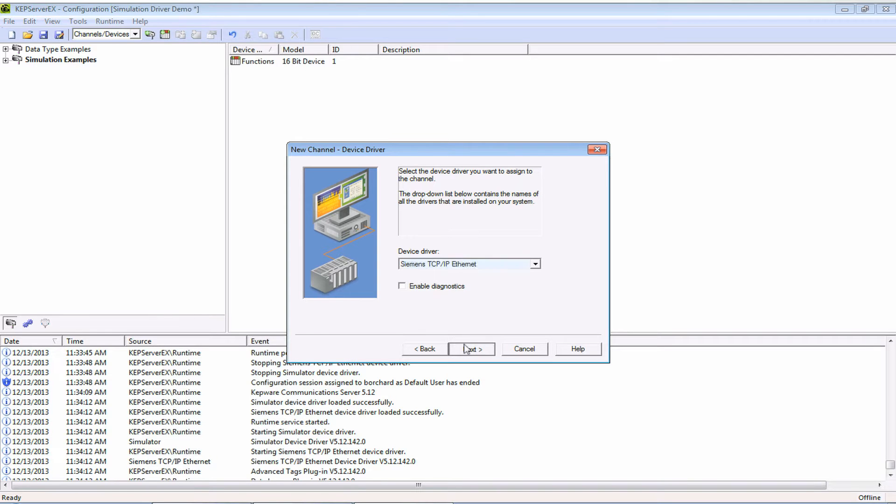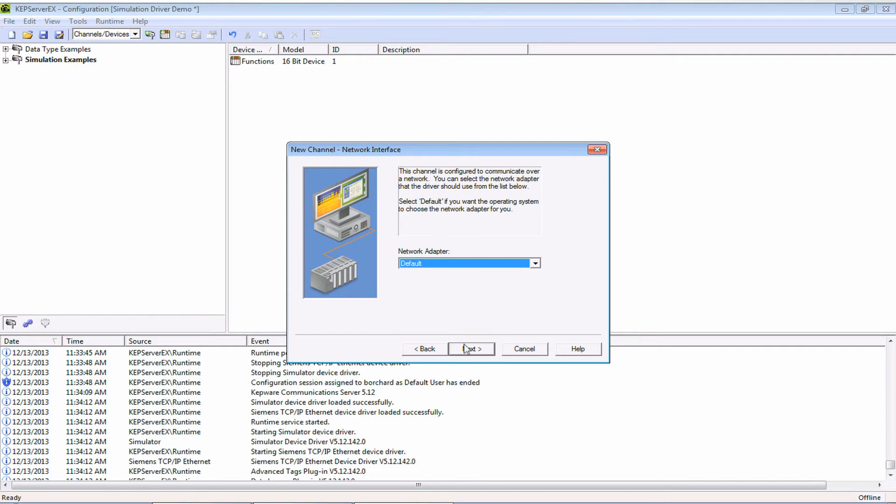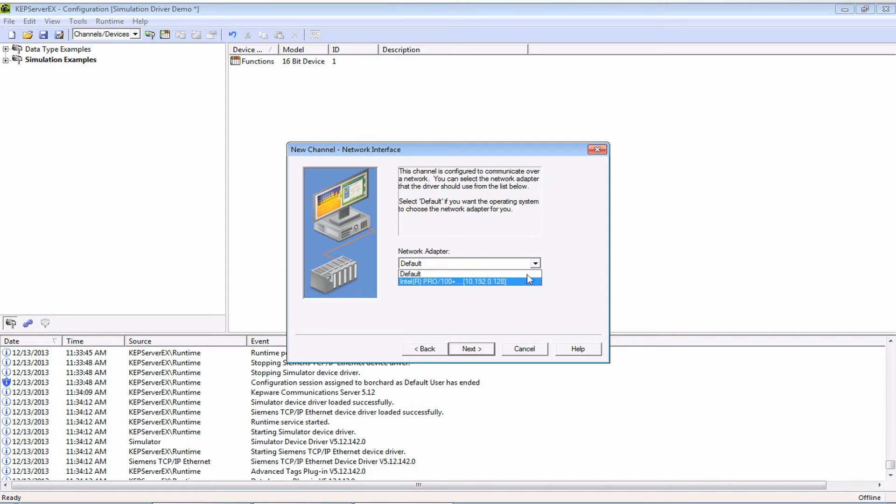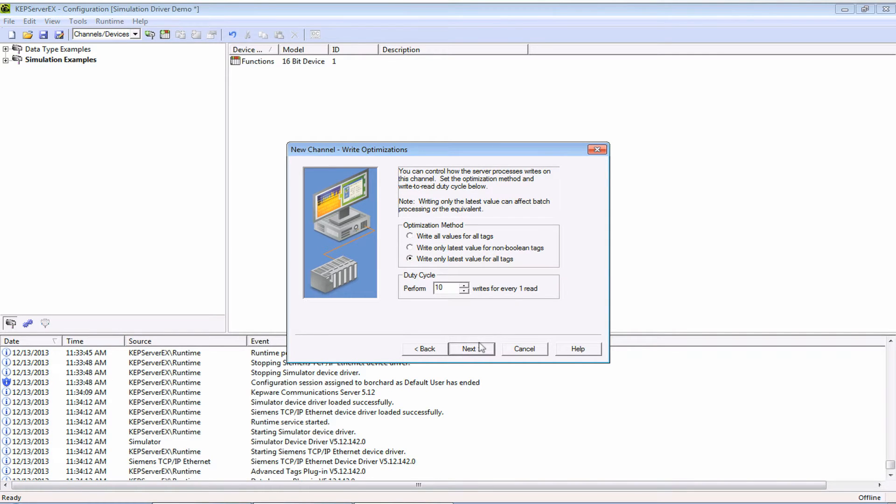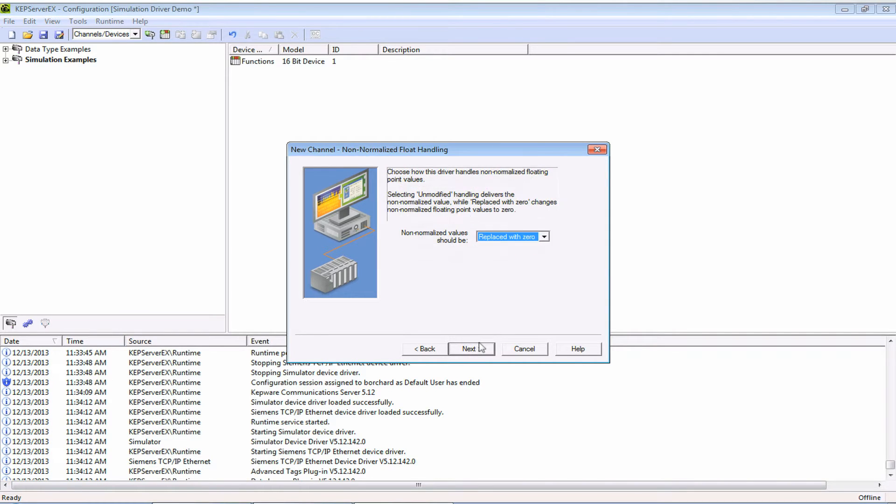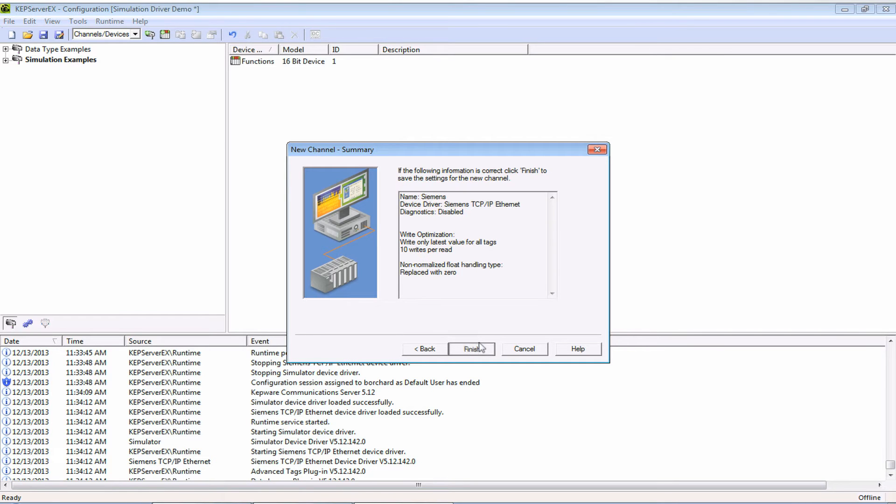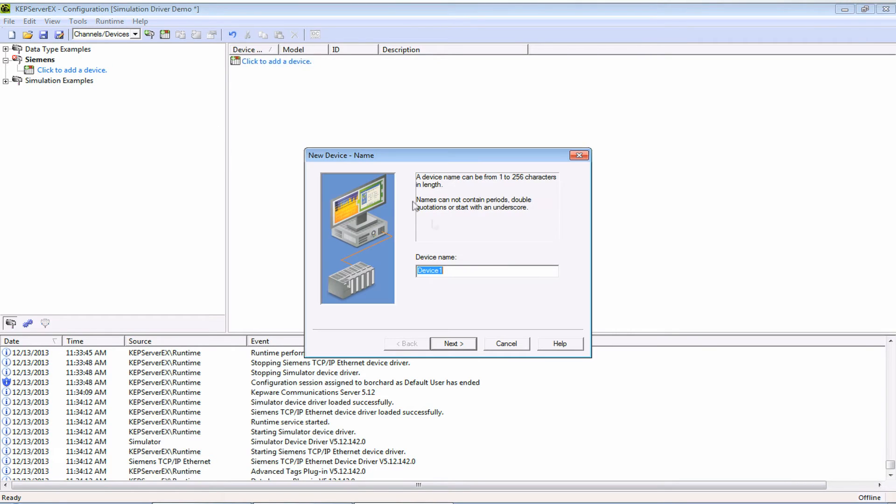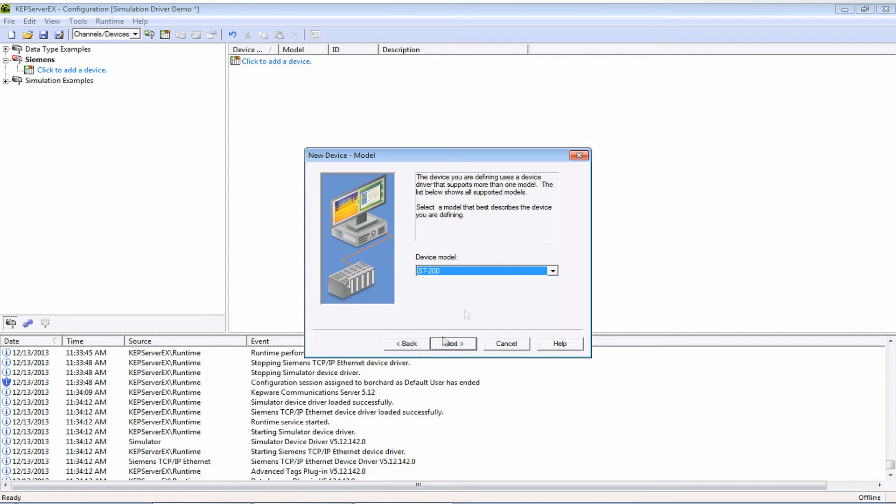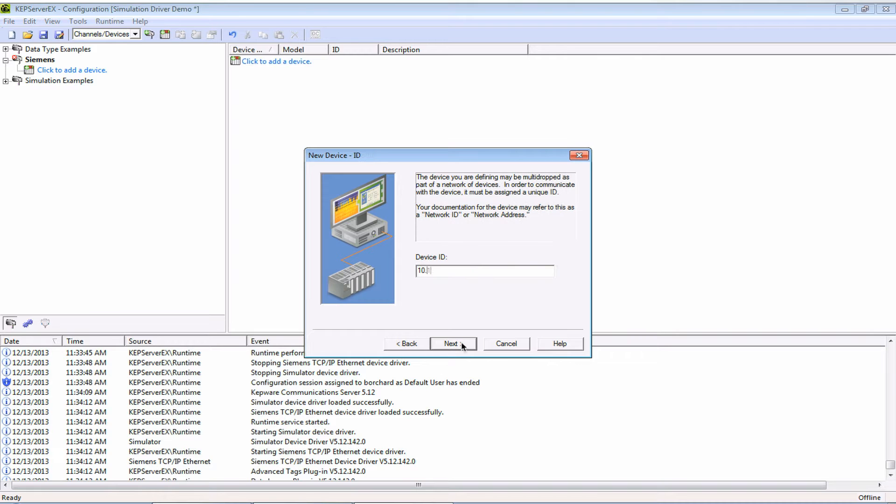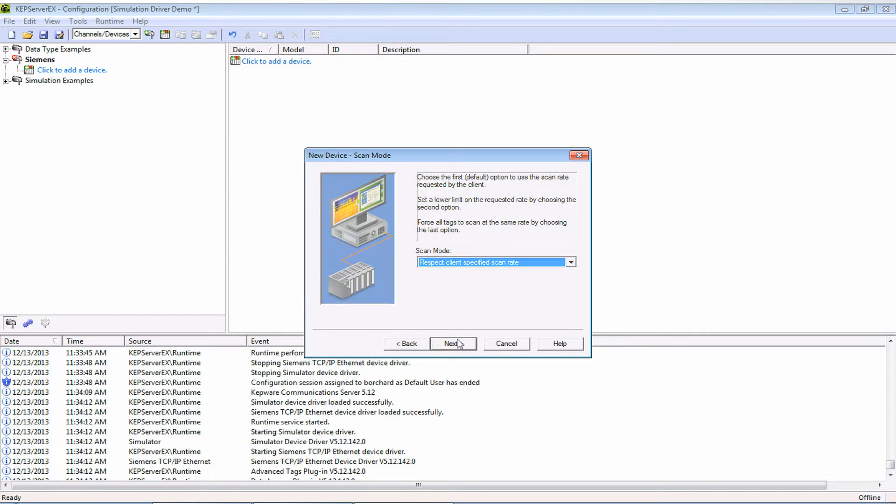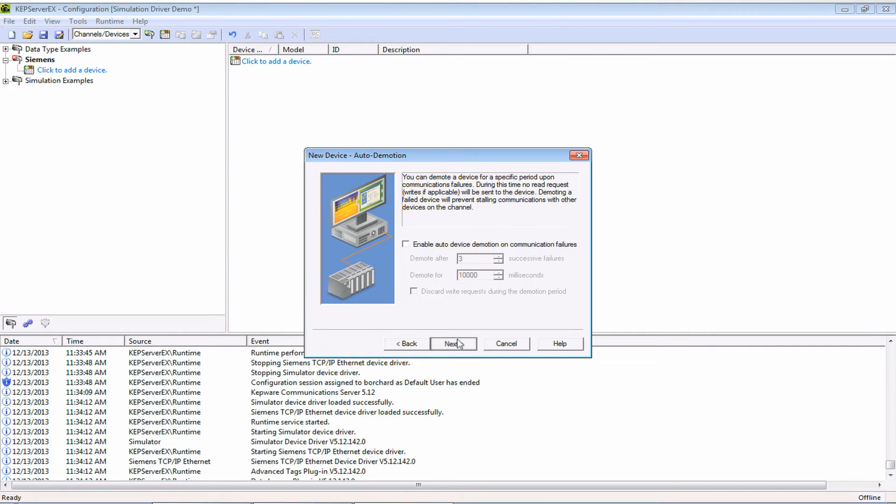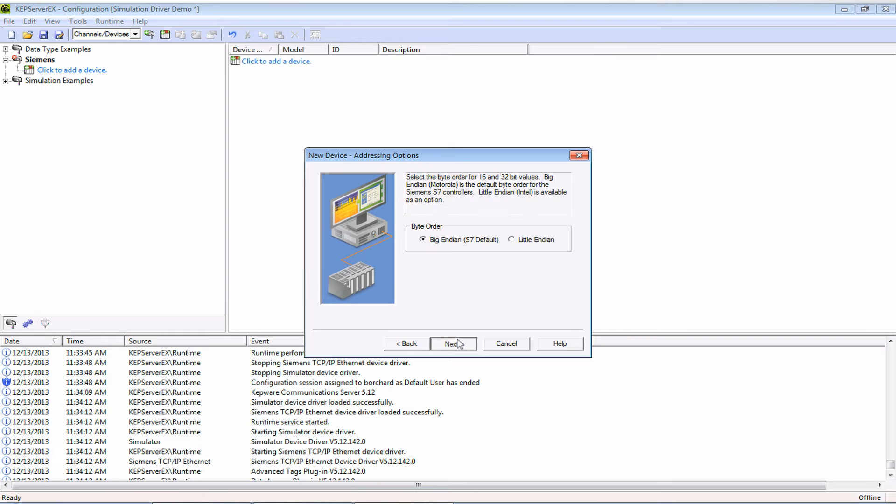Click next and if you have more than one interface card be sure and select the one that the Siemens S7 controller is on. Go ahead and select the defaults for all the remaining dialogues. Now that the channel is created let's go ahead and add a device. I'm going to give it a name, in this case I'm going to call it S7 1513 for my PLC here, and select the device ID which is the IP address. Accept the defaults on the next few dialogues and okay there we go.